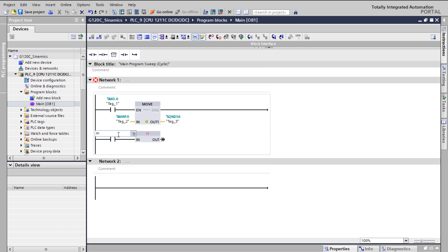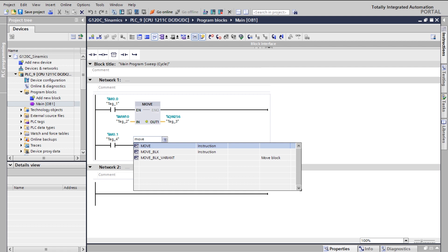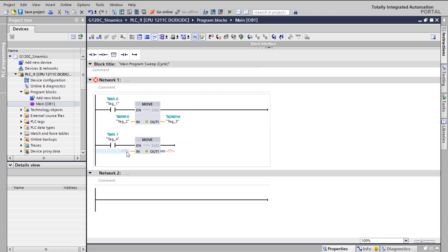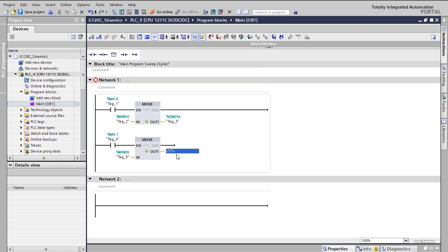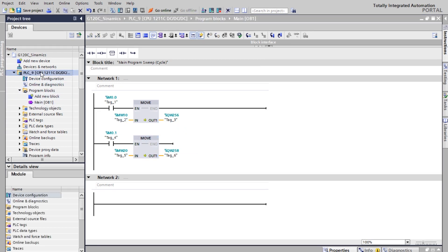The second rung is used for speed. I'm using memory bit M0.1 followed by the MOVE instruction to transfer the speed code. For speed, I'm using memory word register MW20. It's up to you — you can use any memory word register — but make sure for the control word you use QW256 and for the speed use QW258. Whatever you type in the memory register will be transferred to QW256, the control word register.